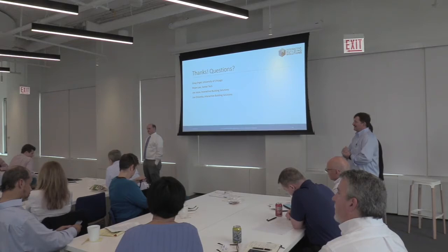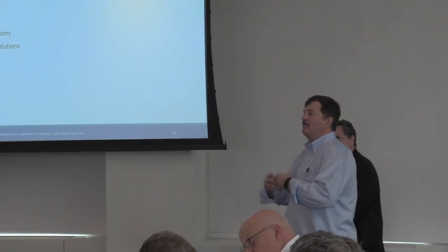Just yesterday, I help a lot of other contractors, and I have a lot of friends that are contractors. Somebody called me and said, "Hey, this professor that we're doing a lab for gave us a criteria to test this vacuum system, and he said it was 3 torr. What's 3 torr?" I happened to be in the same location, so I went to see him. I said, "Well, did you talk to the professor?" He said, "Oh, no, no, no, no. They won't let us talk to the professor at all."